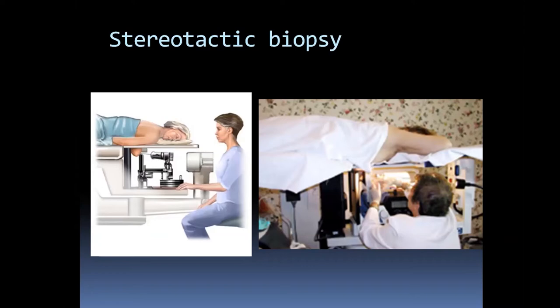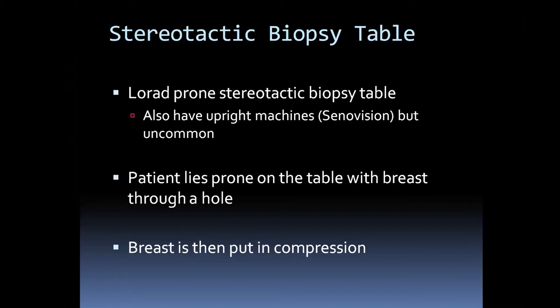A standard mammographic stereotactic biopsy involves the patient lying prone on a table with the breast hanging through a hole. Underneath is essentially a mammogram machine; the breast is against the detector in compression. A great advantage is that the patient cannot see the needle, which is ideal for patients afraid of needles. However, it is not ideal for patients with limited mobility — such as those with spinal fusions — who have difficulty lying on the table. Upright stereotactic biopsies and 3D stereotactic biopsies are also available. At our institution, we use a Lorad prone stereotactic biopsy table, with upright machines also available for attachment to Hologic units.